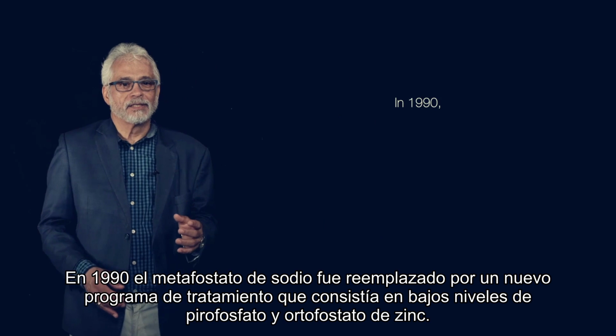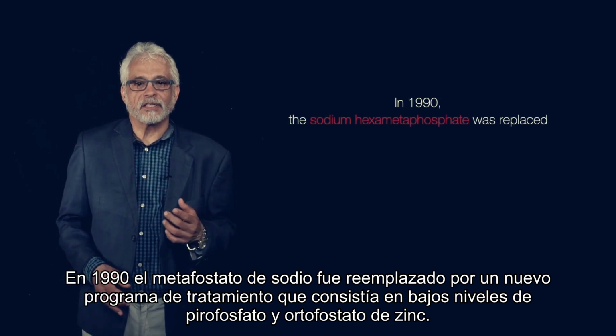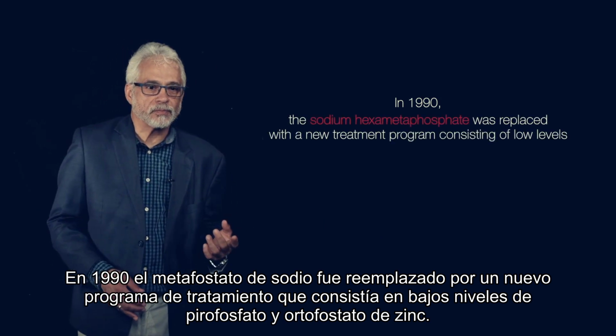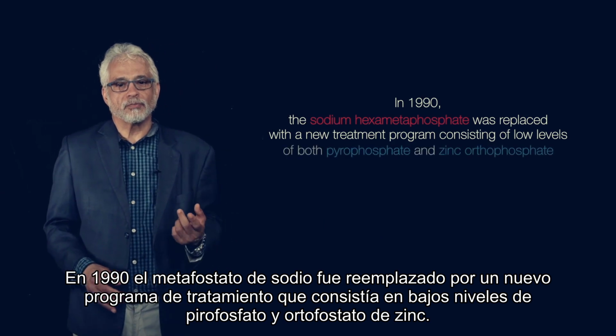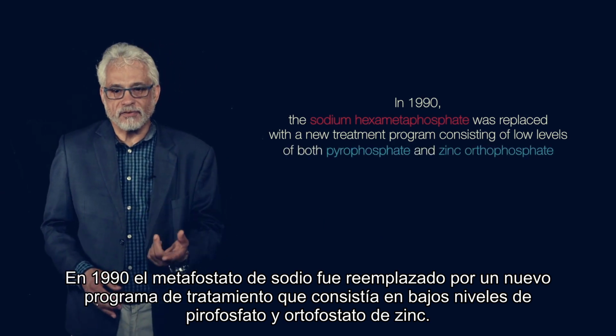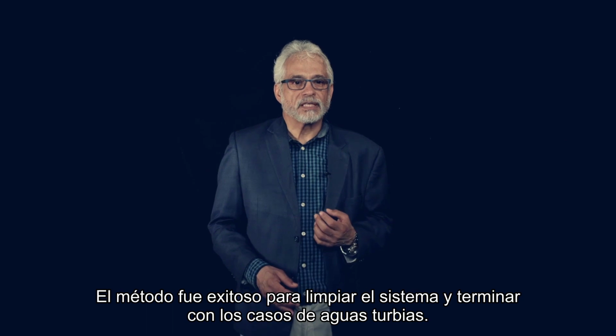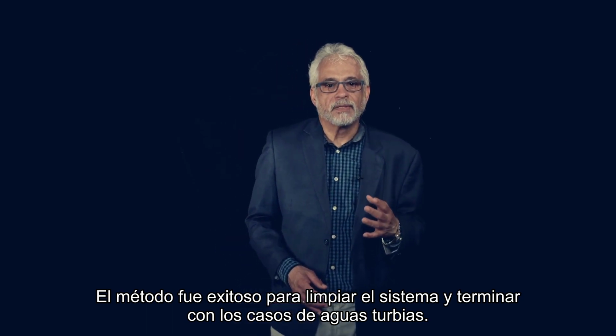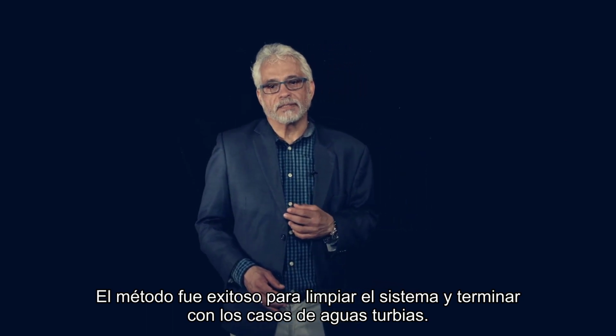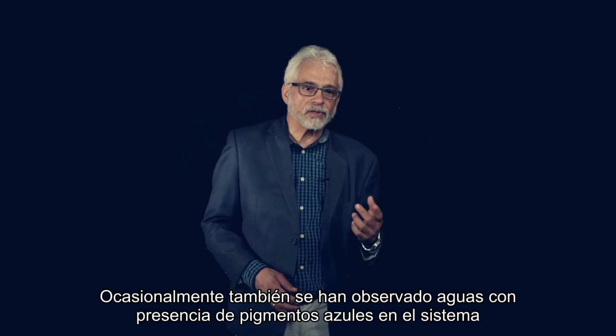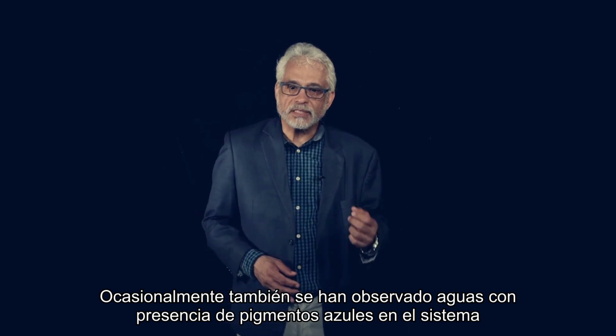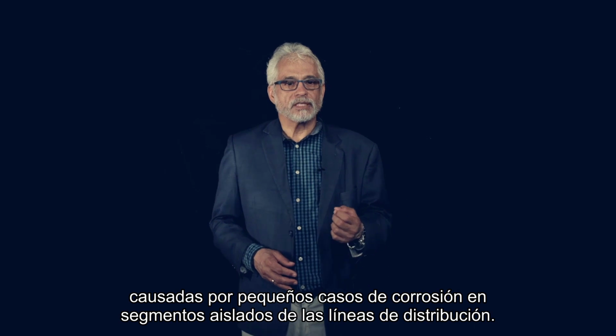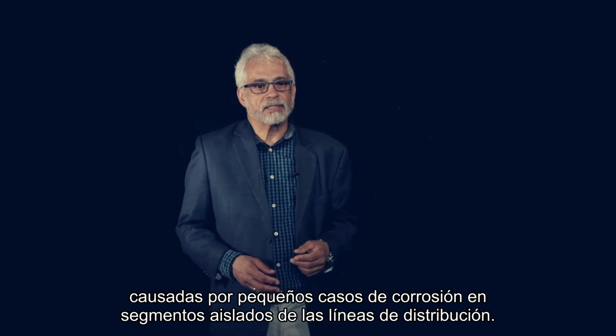In 1990, the sodium hexametaphosphate was replaced with a new treatment program consisting of low levels of both pyrophosphate and zinc orthophosphate, which successfully cleaned up the system and eliminated the brown water complaints. Occasionally, blue water occurrence has also been observed in the distribution system, caused by corrosion in smaller copper distribution lines.